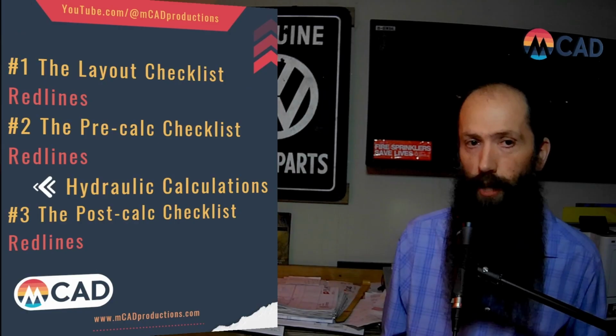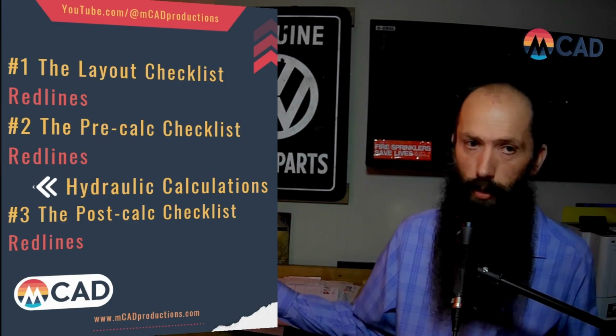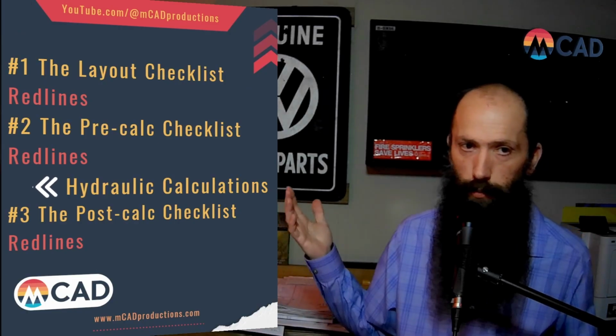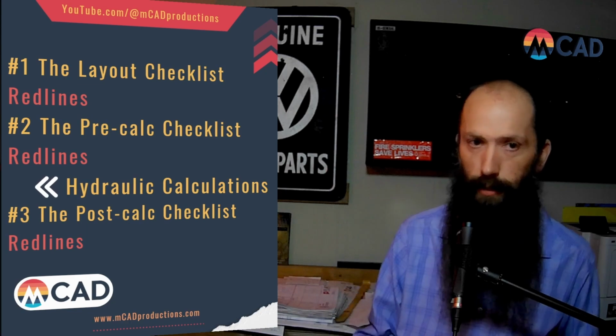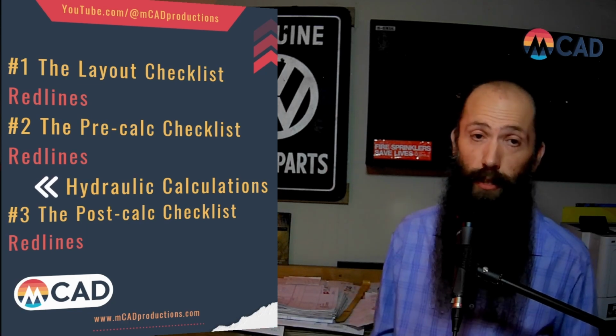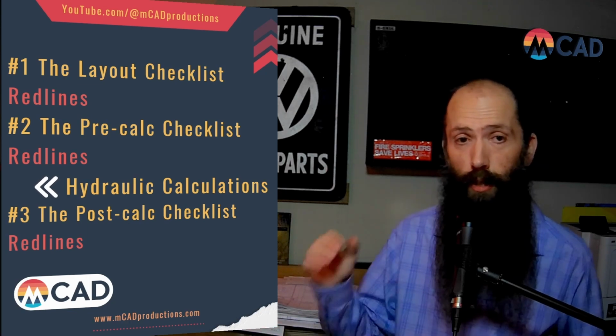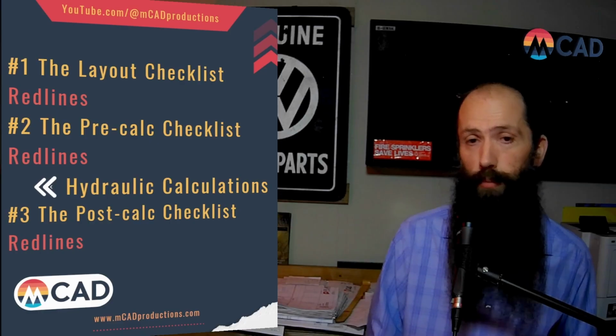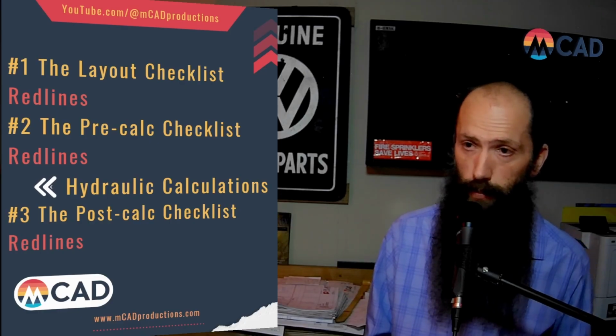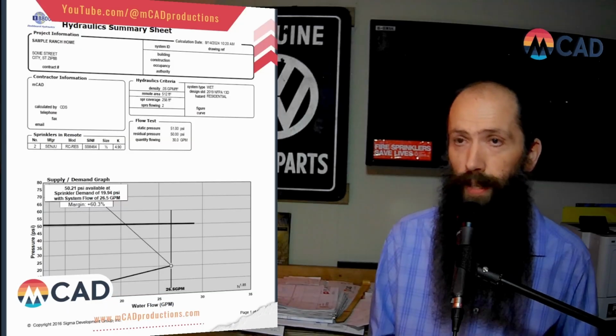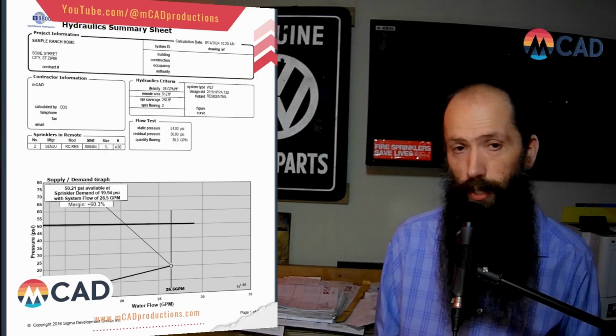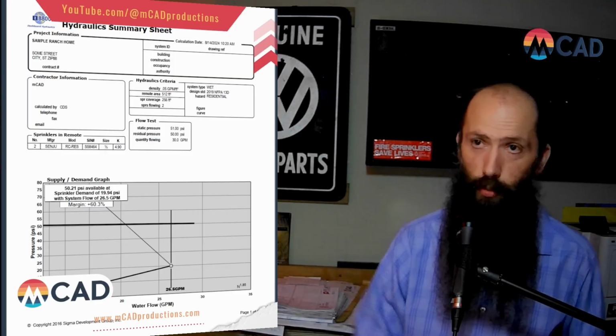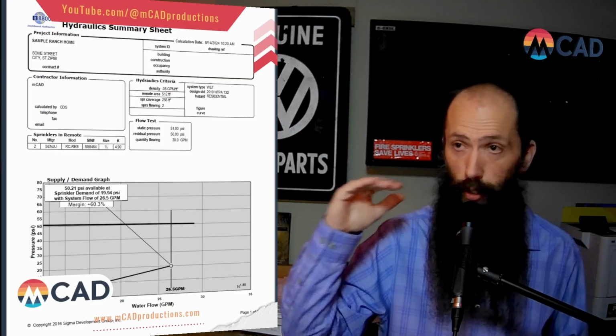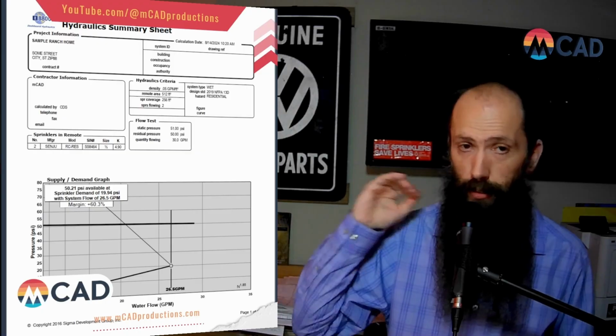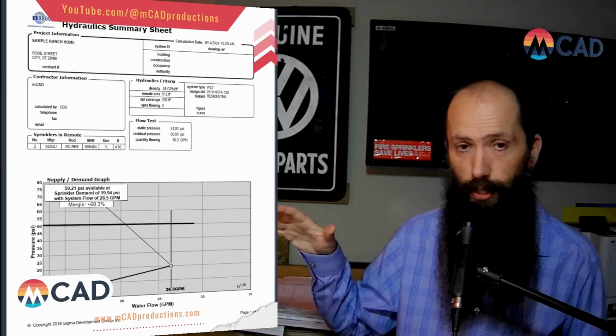All right, and then we talked about in between pre-calc checklist and post-calc checklist implies that there's calcs in between. Those calcs are hydraulic calculations to help us determine the pipe sizing that we need to make our sprinkler system work. And so we went through in our live lectures how to read this report for the calc that we did for this project.